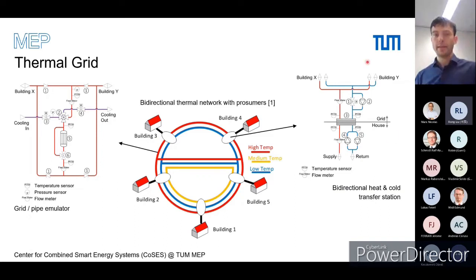On the right side, you see the bidirectional heat and cooling transfer station, where we can change the flow direction on the house side. And if we're in the feed-in state on the grid side, we need to overcome the pressure difference in the grid, so we need an extra pump in addition to the control valve.